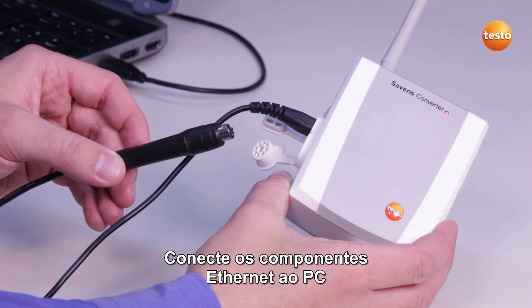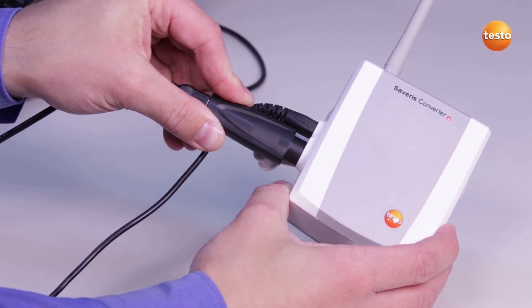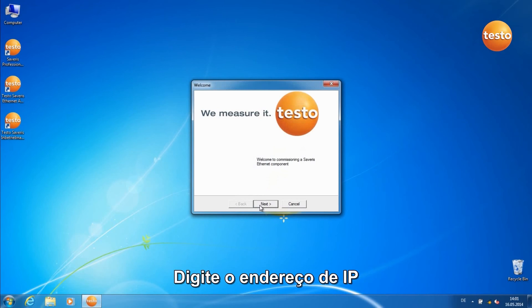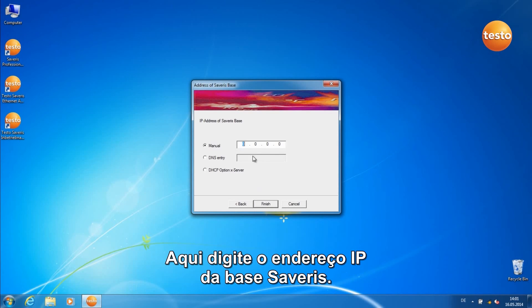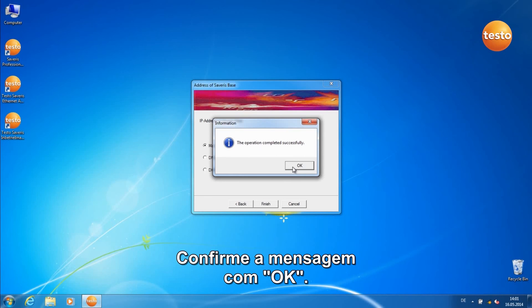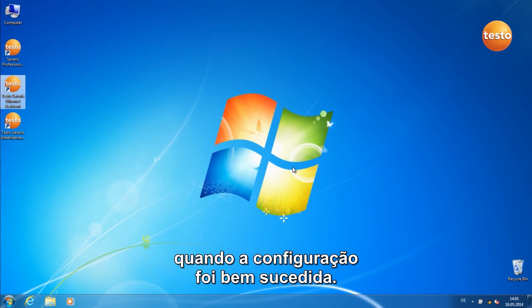Connect the Ethernet components to the PC using a USB cable and programming adapter. Now start the Testo Saveris Ethernet Assistant. Enter the IP address, net mask, and gateway of the components. Here enter the IP address of the Saveris base. Click on Finish. Confirm the message with OK — the component now runs down and briefly lights up green when the configuration was successful.